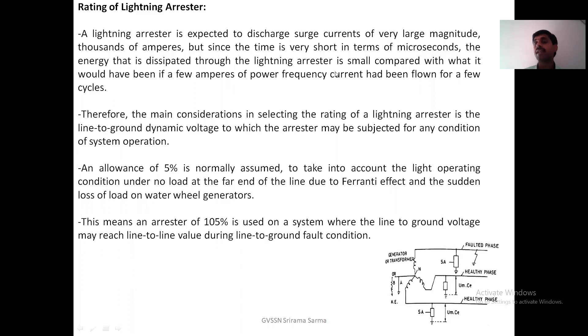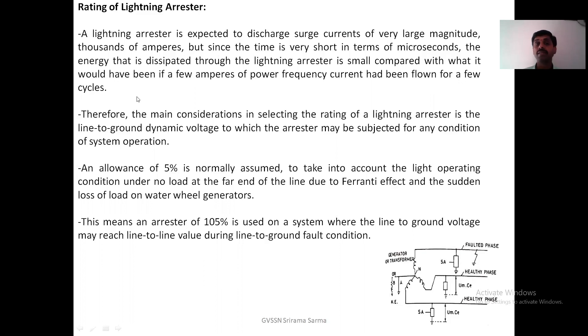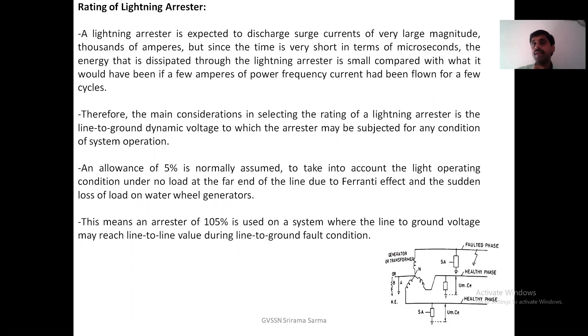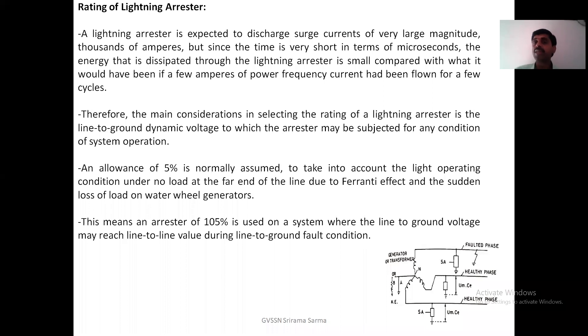The energy dissipated through the lightning arrester is very small because the current is large but the time is very short. Compare this to what would happen if a few amperes of power frequency current flowed for a few seconds — that would have more energy. Large current flowing for microseconds has less energy. That is why, compared to normal frequency current, the energy associated with lightning current is very small.